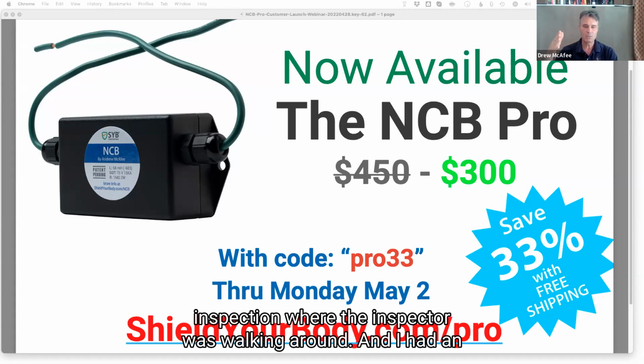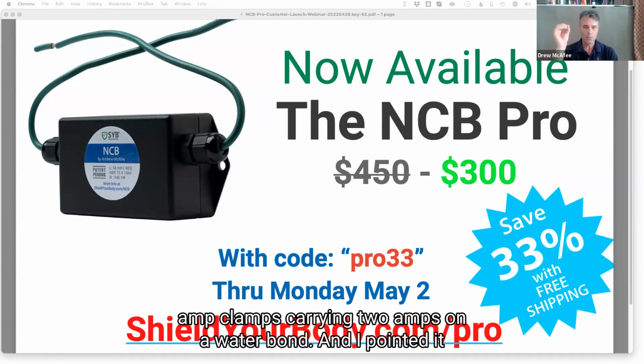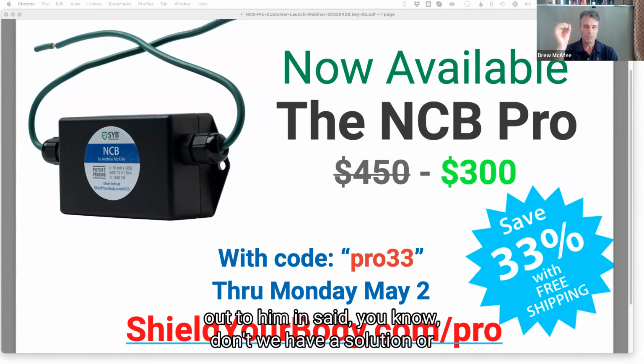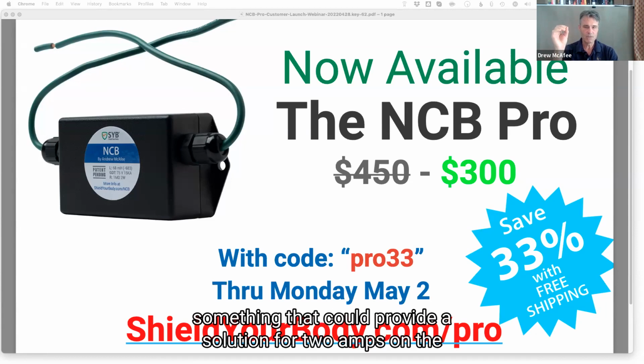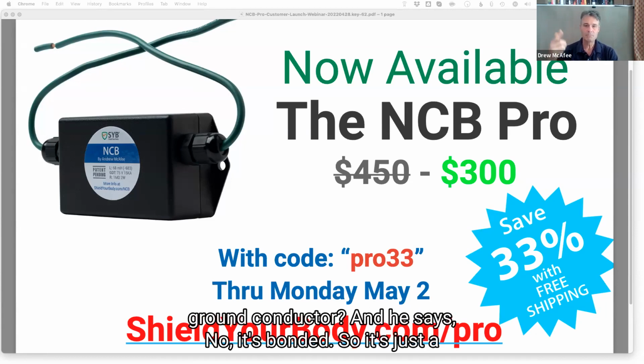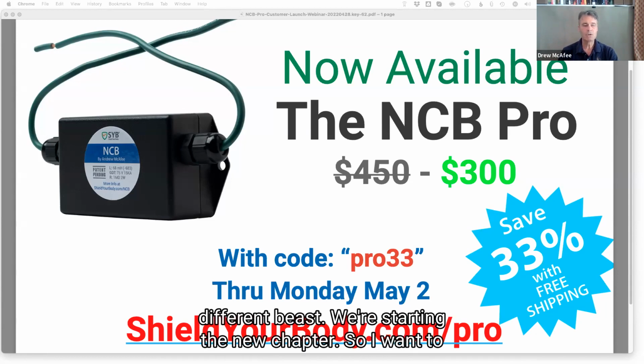I was in an inspection where the inspector was walking around and I had an amp clamp carrying 2 amps on a water bond. I pointed it out to him and said, don't we have a solution or something that could provide a solution for 2 amps on the grounding conductor. And he said, nope, it's bonded. So it's just a different beast. We're starting a new chapter.